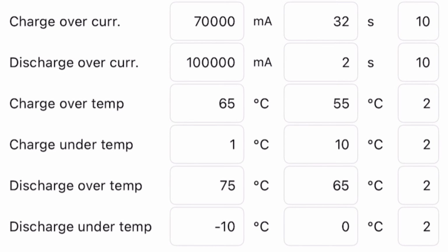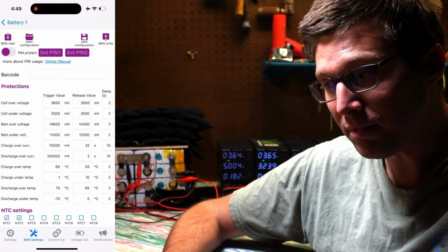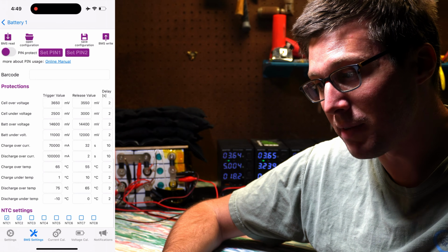The discharge temperature is set low because when you draw a big load it warms the batteries up, keeping them in a happy temperature range. If you're not around and they're charging, it's a bit more stringent on when charging is allowed. That's how I set the BMS.